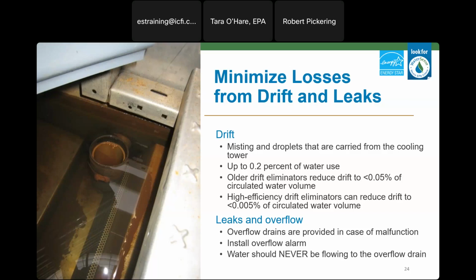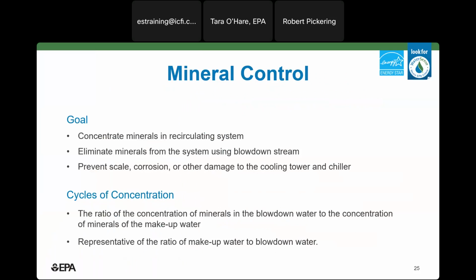The primary opportunity to improve water efficiency of a cooling tower is really in reducing the amount of blowdown by concentrating minerals in the recirculating system. For background, as the mineral concentration rises in the tower, the blowdown stream will discharge a certain amount of water and replace it with city water, thus reducing the overall concentration of minerals in the system. So mineral control and blowdown is necessary to protect the cooling tower and chiller equipment and to prevent the formation of scale, corrosion, or biological growth.